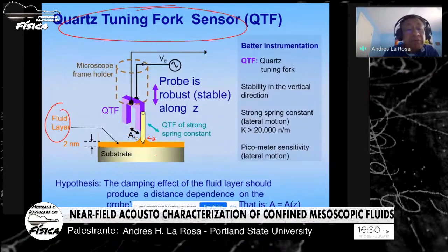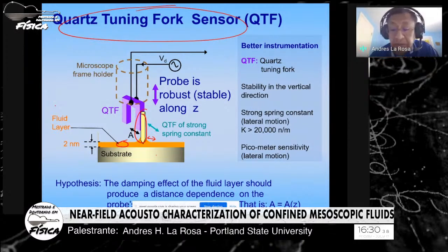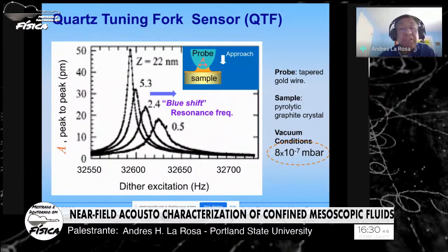Why can it not be viscous? It is because if it were viscous forces, an interaction between the probe and the fluid, its resonance frequency should shift to the left. However, and this is when I was a graduate student, as a curiosity, the next is not my data, but was published later on, in which they approach the sample vertically with the probe, and at each distance you run a spectral response. Therefore, you measure its resonant frequencies at different vertical positions, far away from the sample, closer.